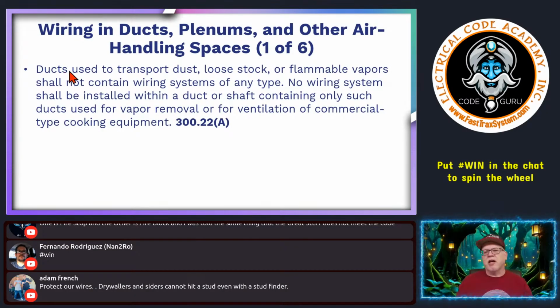Ducts used to transport dust, loose stock, or flammable vapors shall not contain any type of wiring system. That's a no-brainer. No wiring system shall be installed within ducts or shafts containing only such ducts used in vapor removal or ventilation, commercial type cooking vents, and all that.